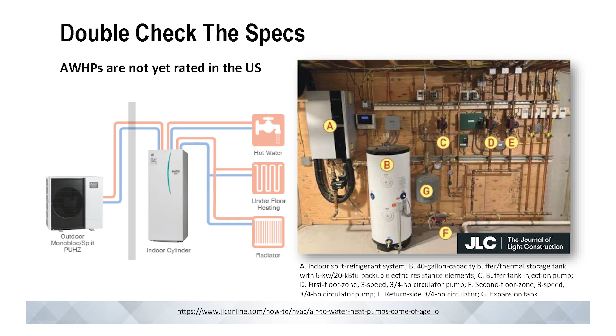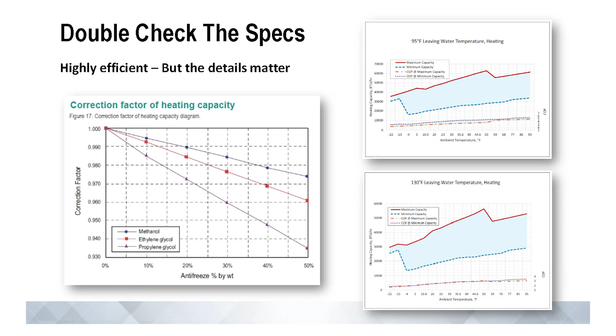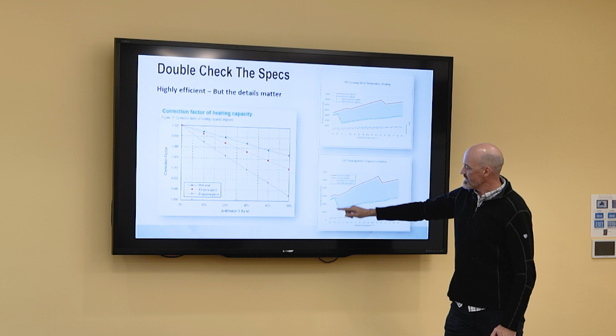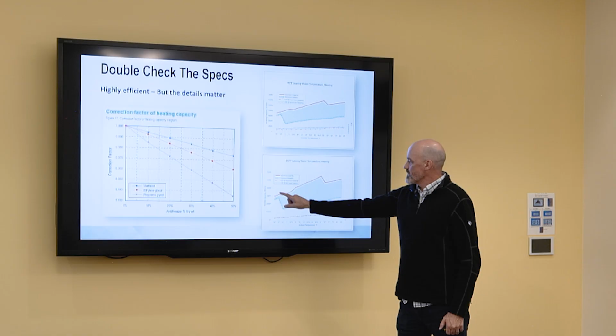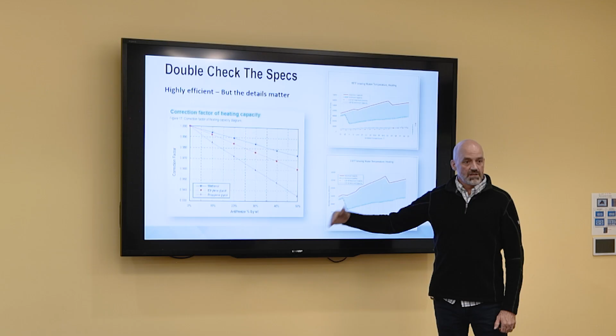These systems are highly efficient, but you've got to double check the specs. Since we don't have that one chart, here I pulled up the performance chart of a particular model, a very good model, but you can see it definitely drops. This is 95 degree water as it leaves the unit, and this is 130 degree water as it leaves the unit. This system needs to deliver hotter water to the house, but you're not going to get as much out of it at these low temperatures, negative 13, negative 20, etc. That's where your supplemental is going to show up. But it will operate down that low, you just have to have that supplemental, an inline resistive heater, etc.